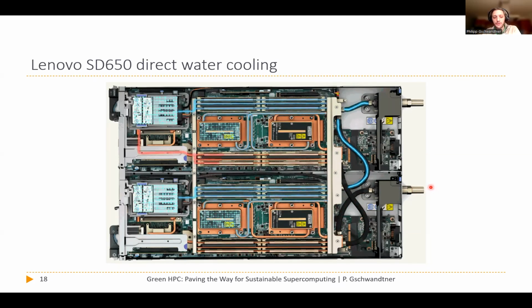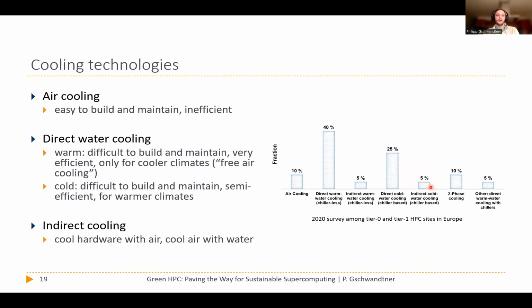There are a couple of technologies or methods for how to do it, which gets us to the next slide, because cooling the nodes is only one part of it. If you cool the nodes, you put cold water in and get warm or hot water out, but now you have this temperature gradient and you need to bring the hot water down to the cold level again to be able to push it back into the nodes. And there are multiple different means of doing this.